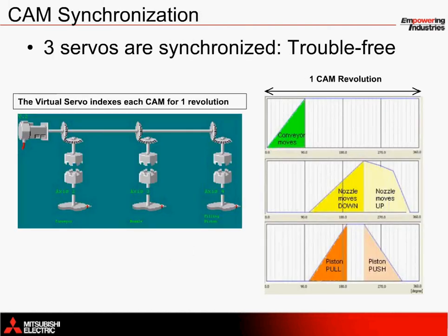A closer look at these cam profiles helps to illustrate what's happening behind the scenes. The conveyor axis, axis number 2, uses a feed cam profile to index the conveyor for one-fourth of its entire rotation. For the rest of the profile, even though the cam itself is rotating, the servomotor does not move. This is because the profile has already reached 100% of its stroke setting.